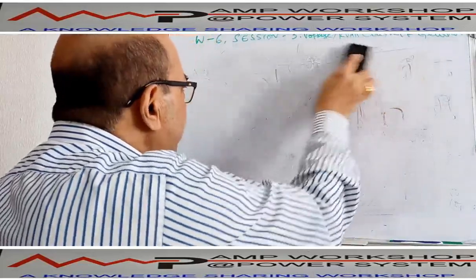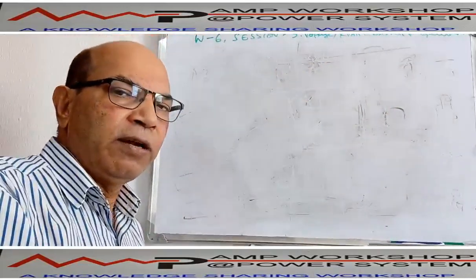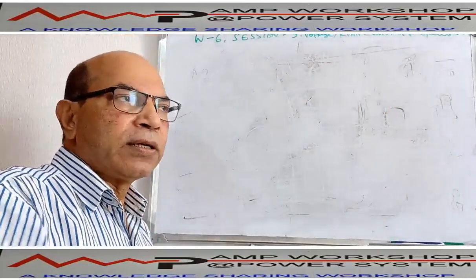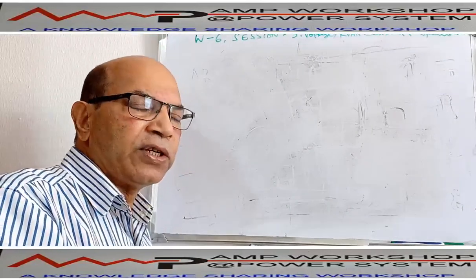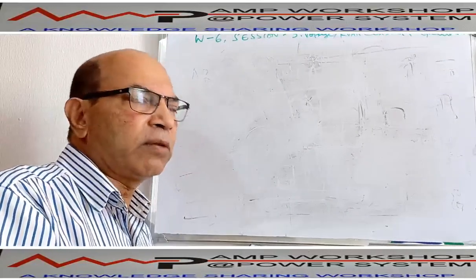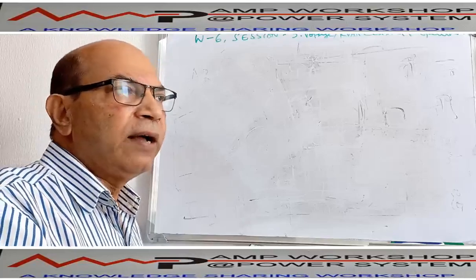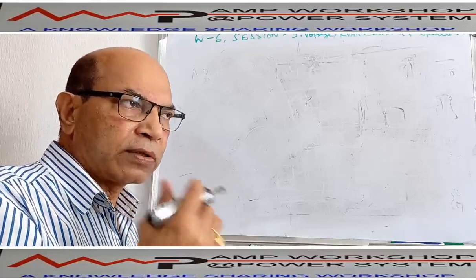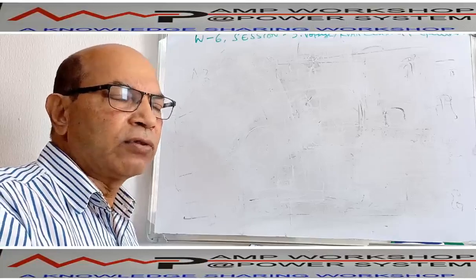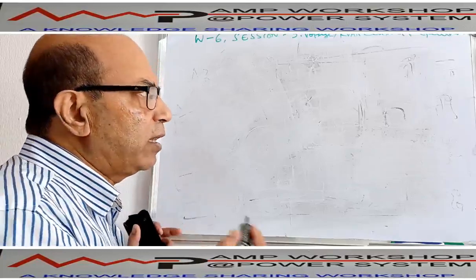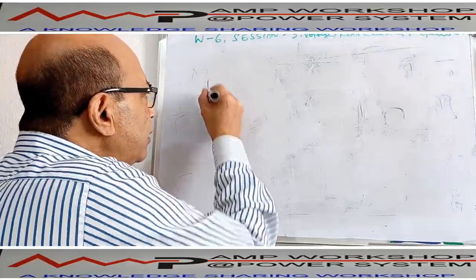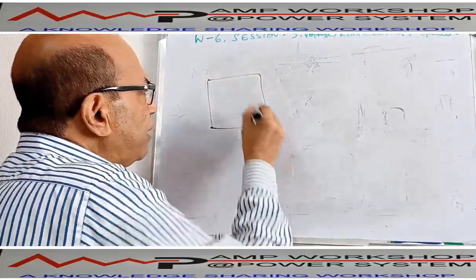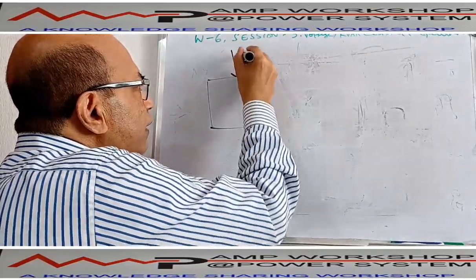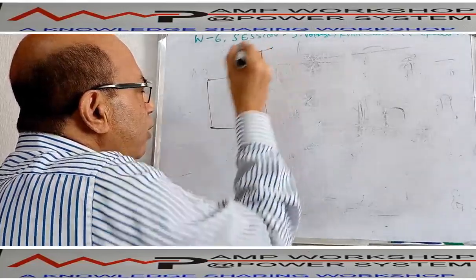If we look into the automatic voltage regulator, it has an input section where there are three inputs. One input is a CT input for the cross current compensation. The second input is the actual voltage of the generator. The third input is the control voltage, the supply voltage we are taking to the thyristor, for powering the thyristor block in the power section. So these are the three inputs we have to keep in mind. One input is a PT input for the actual voltage.